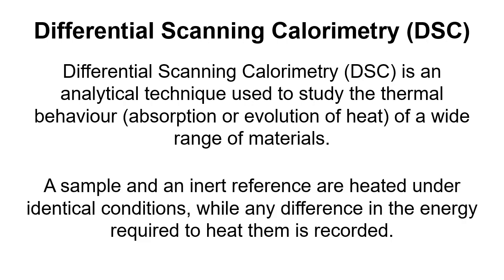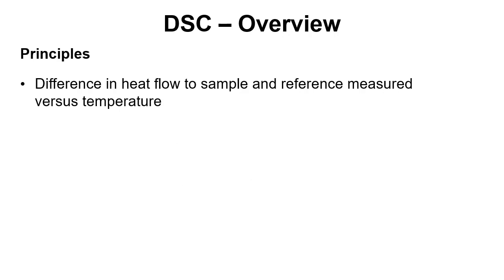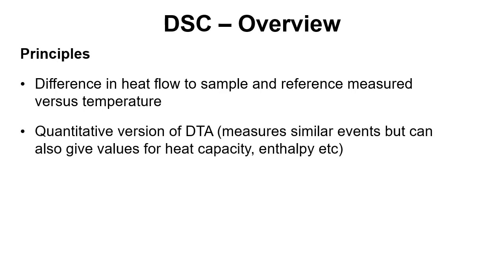A sample and an inert reference are heated up under identical conditions and any difference in the energy required to heat them is recorded. The basic principle is that we're monitoring the difference in heat flow to a sample and reference versus temperature. It can be thought of as a quantitative version of a DTA — it measures very similar events but can also give values for enthalpy and heat capacity, so it gives the energy associated with different thermal events. DTA can only tell you the temperatures at which events are occurring, whereas DSC gives you the energy associated with them.